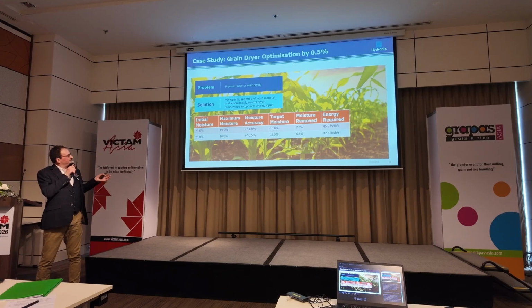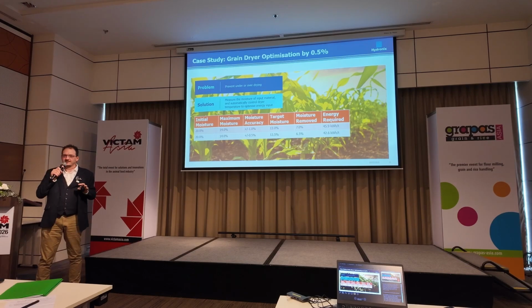So they were looking to dry the material they were processing from 20% down to 14%. With their original moisture system, they reckoned they could get about 1% accuracy, so they had to target 13% moisture to make sure they were always under that. The moisture you're removing at that point is 7%, and we can calculate that at about 45.9 kilowatt hours per tonne.